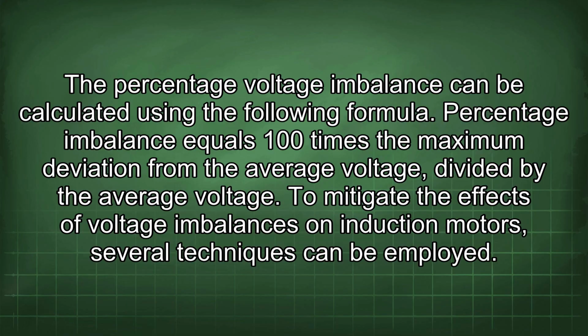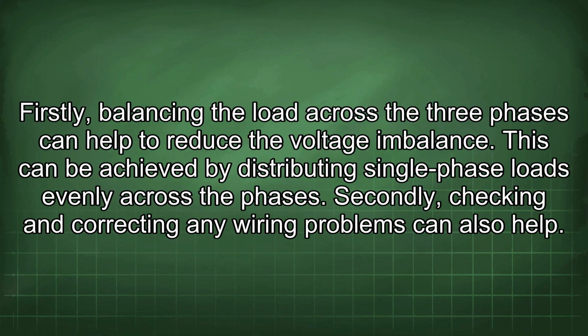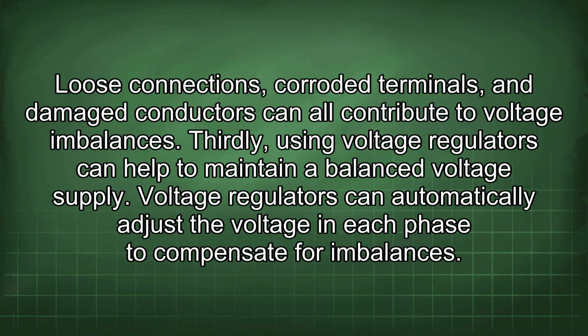To mitigate the effects of voltage imbalances on induction motors, several techniques can be employed. Firstly, balancing the load across the three phases can help to reduce the voltage imbalance. This can be achieved by distributing single-phase loads evenly across the phases. Secondly, checking and correcting any wiring problems can also help. Loose connections, corroded terminals, and damaged conductors can all contribute to voltage imbalances. Thirdly, using voltage regulators can help to maintain a balanced voltage supply. Voltage regulators can automatically adjust the voltage in each phase to compensate for imbalances.